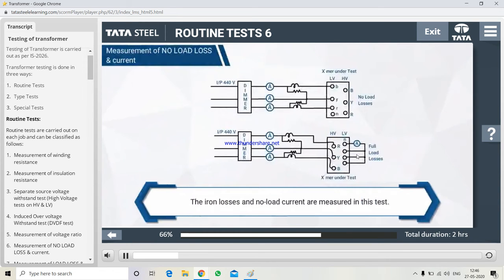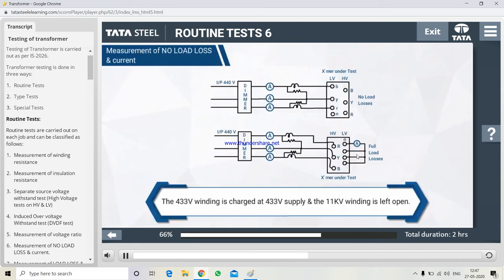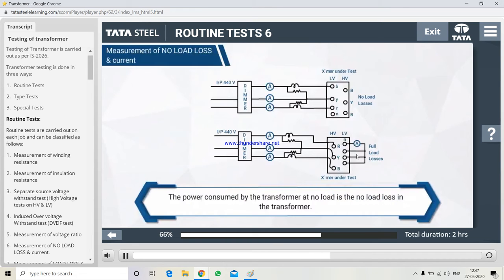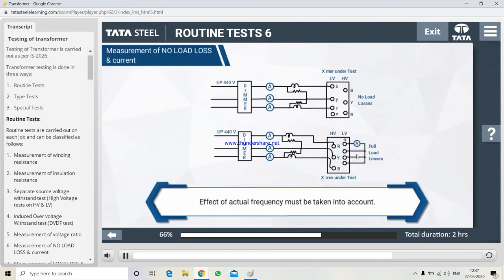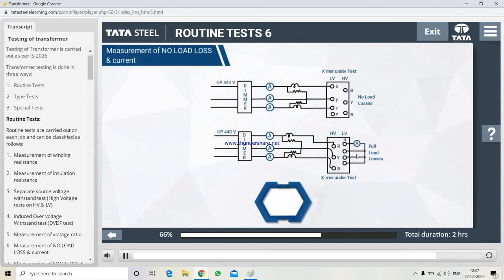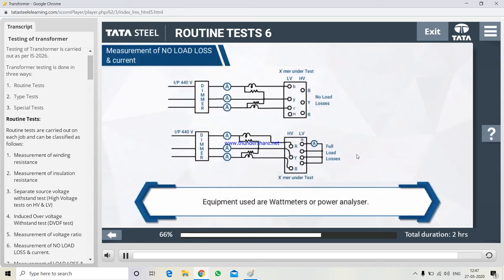The iron losses and no load current are measured in the test. The 433V winding is charged at 433V supply and the 11 kV winding is left open. The power consumed by the transformer at no load is the no load loss in the transformer. Effect of actual frequency must be taken into account. Equipment used are watt meters or power analyzer.